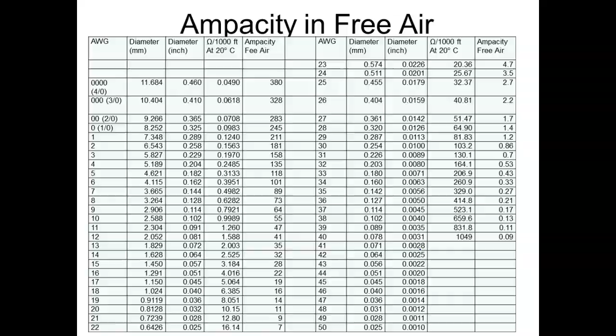Then we looked at the NEC code that they derate these things so much. So here it says 14 gauge wire should only be rated at 15 amps if it uses these types of insulation.